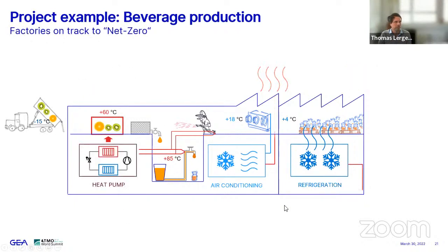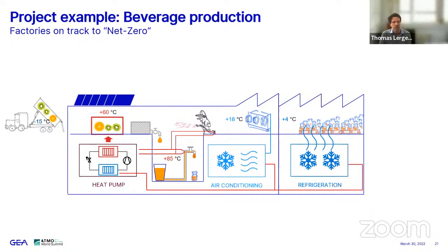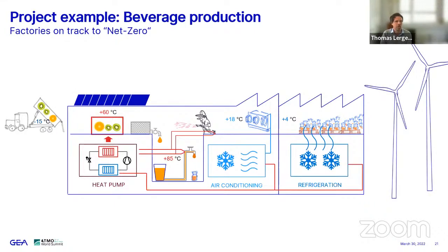And if factories want to be on the track to net zero, then they replace the boiler by a heat pump. In this case, we were able to use the waste heat from the aircon and the refrigeration system. It goes directly into the heat pump, and then the heat pump can provide the capacities and temperatures that the boiler could also do. Here it's doing it, of course, not just more efficiently, also on an economic basis. There are several of these factories, but there's a specific location in the Netherlands, and they put some solar panels on the top, and there's a wind park close to the factory, which they can also hook up to. So this is really a green factory, because they're now getting the electricity only from their solar panels and from the wind park. They have really done their homework. They already have their track to net zero. They're already very, very far on this one.